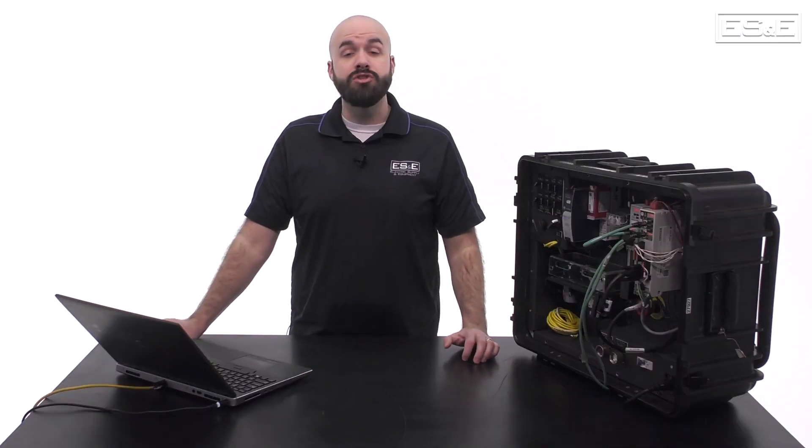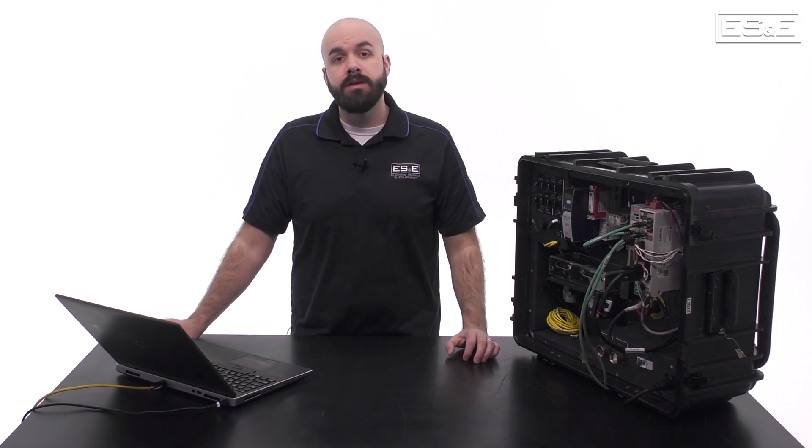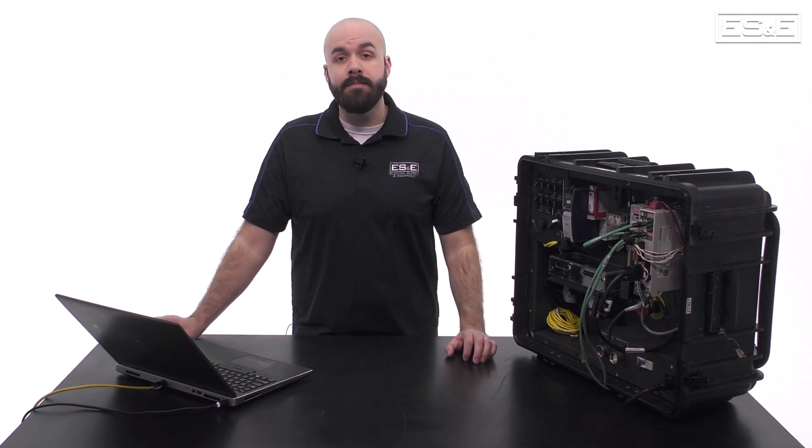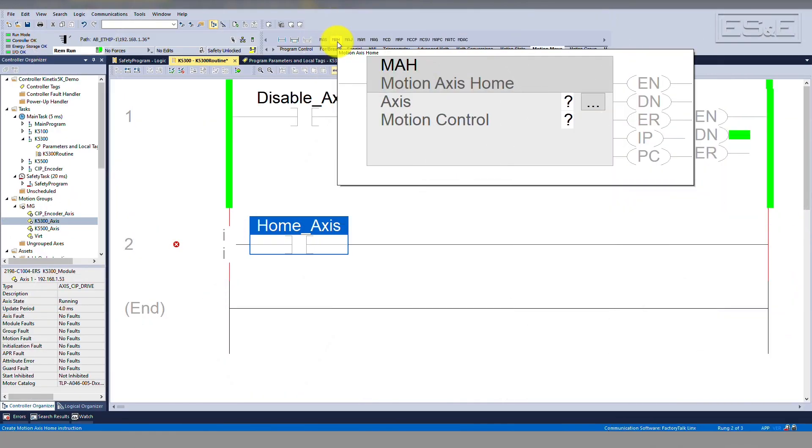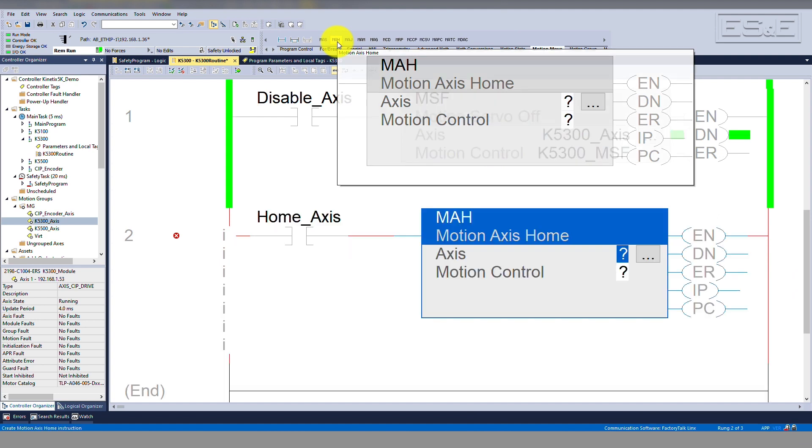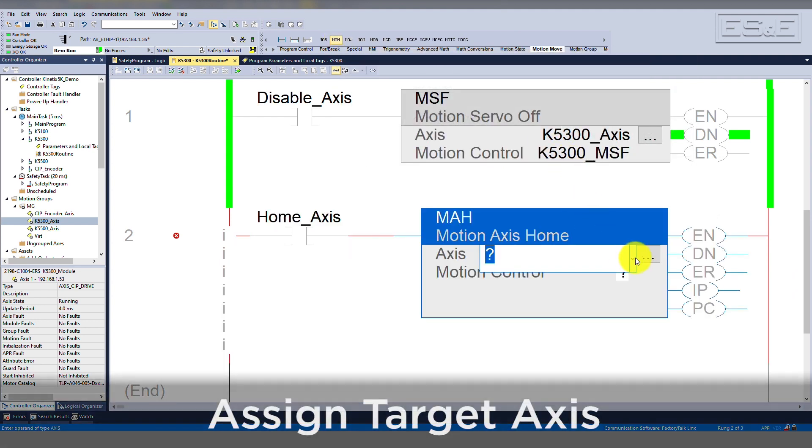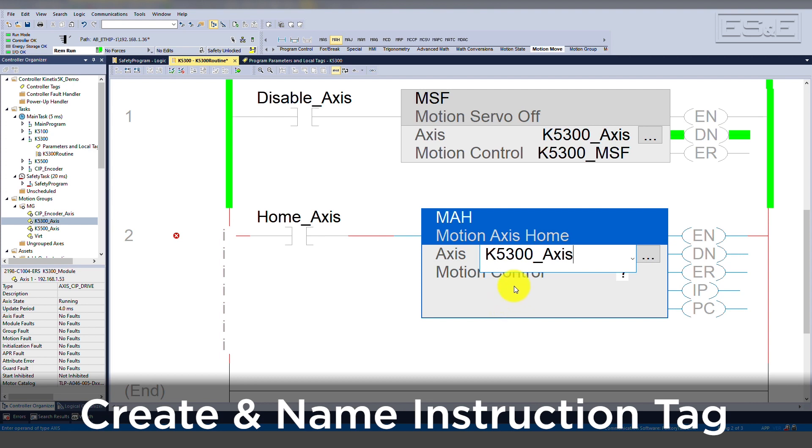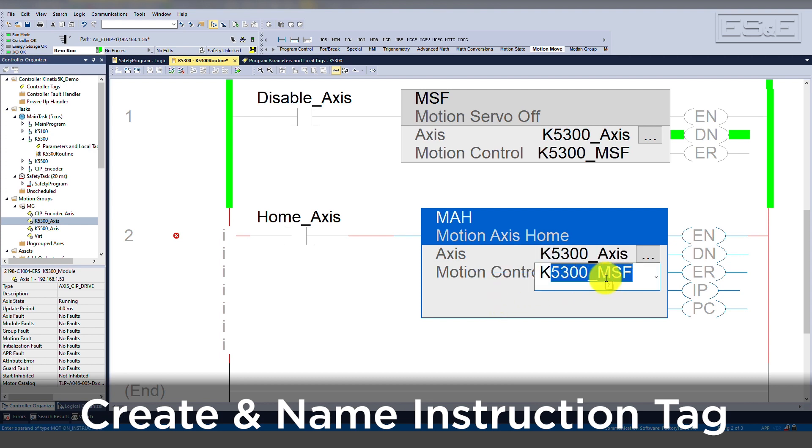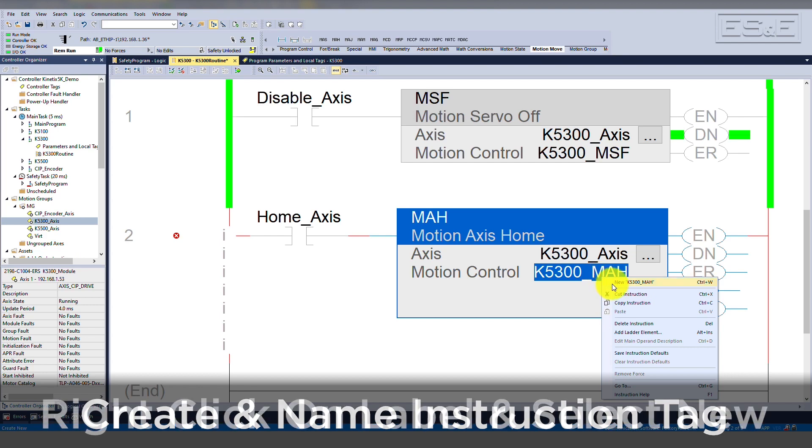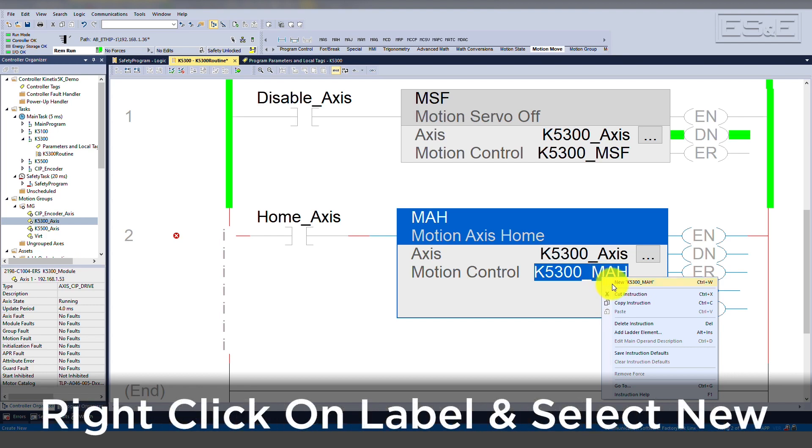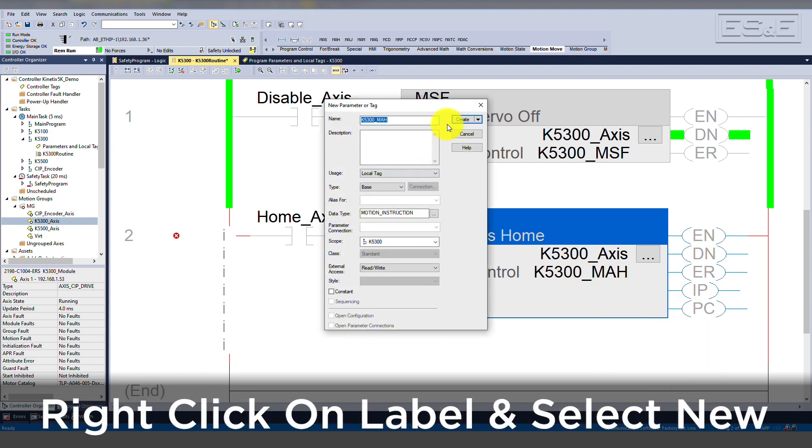Now let's build the instruction in LadderLogic. You can find the MAH instruction under the Motion Move tab of the LadderLogic instruction selector. Assign the target axis. Create an instruction tag. It's a good idea to name the instruction tag after the instruction itself. That way, when troubleshooting in the future, it will be easier to find the tag.